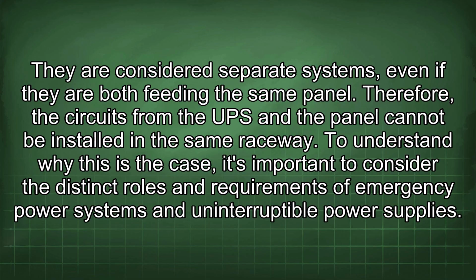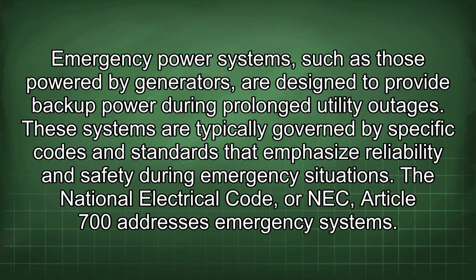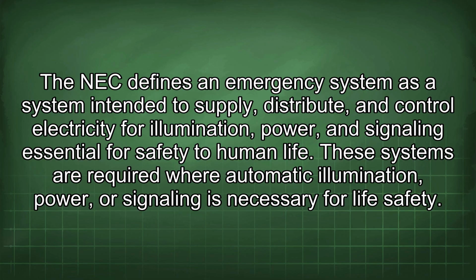To understand why this is the case, it's important to consider the distinct roles and requirements of emergency power systems and uninterruptible power supplies. Emergency power systems, such as those powered by generators, are designed to provide backup power during prolonged utility outages. These systems are typically governed by specific codes and standards that emphasize reliability and safety during emergency situations. The National Electrical Code, or NEC, Article 700 addresses emergency systems. The NEC defines an emergency system as a system intended to supply, distribute, and control electricity for illumination, power, and signaling essential for safety to human life. These systems are required where automatic illumination, power, or signaling is necessary for life safety.